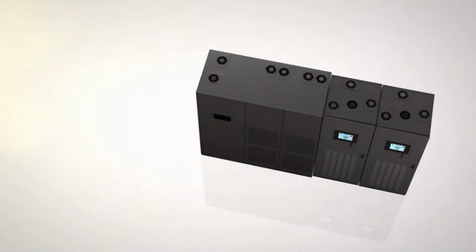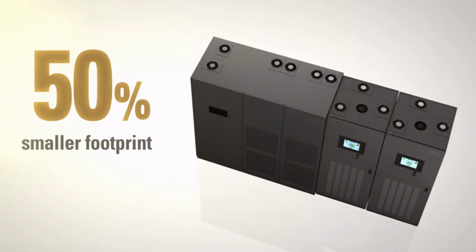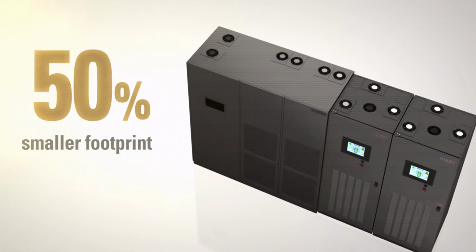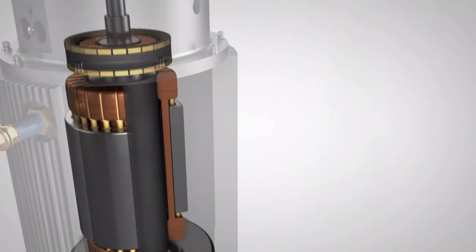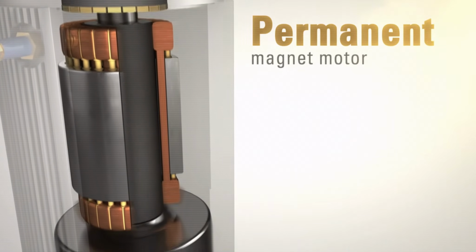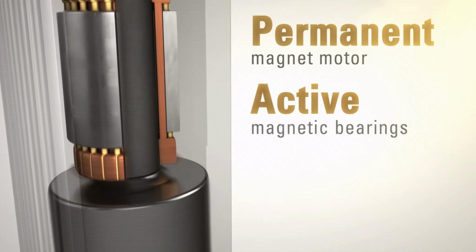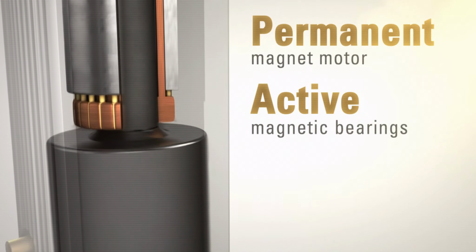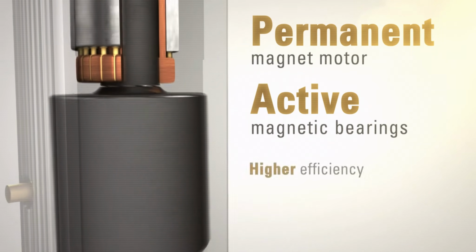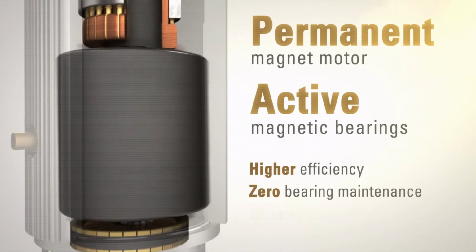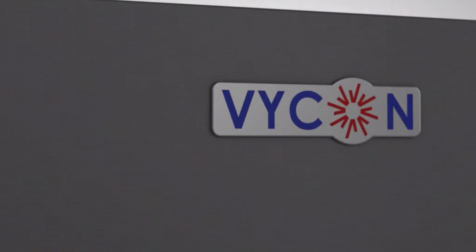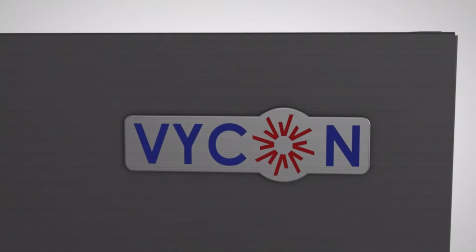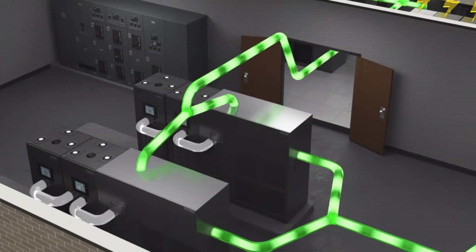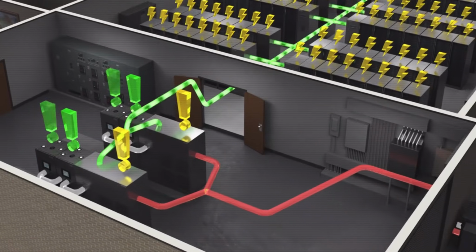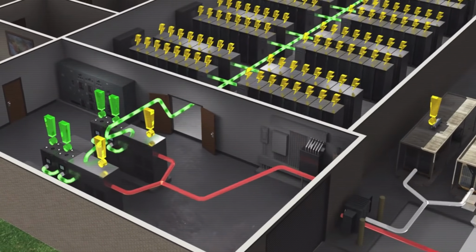Not one. And Vycon's own published cycle rating puts this thing at over 1 million full discharge cycles. A comparable battery UPS sized for the same duty would need a full replacement bank roughly every 4 to 5 years. Modeling an installed cost of approximately $140,000 against a battery alternative that needs repurchasing every half decade, the math stopped being close somewhere around year 7, and it just kept widening from there.